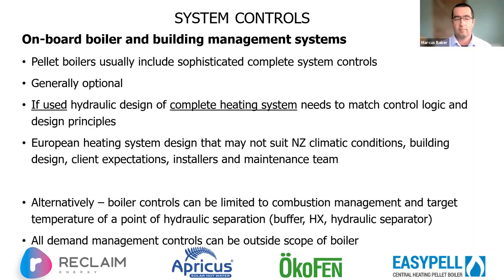My preference, it's only a preference, but maybe as strong as a recommendation, is that the boiler control manages the combustion on the boiler. There's a lot of quite complicated stuff that goes on that side, and it needs to do it. And then it just meets a target temperature at some point of hydraulic separation, be that a buffer or heat exchanger or just a simple hydraulic separator. And then the demand management controls are outside the scope and integrated in the BMS or in some other system. But the boiler is essentially blind to where its heat is going, because otherwise, if the boiler's in control, it's going to need to be completely in control, and you'll need to really understand very well how that control logic works.